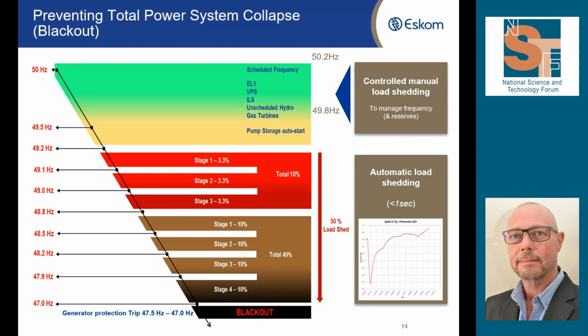What you see in this graphic in front of you now, we have the green portion, which is what I've just described. This is kind of normal operations where things happen fairly slowly, minutes to hours, and we dispatch various generation and demand response products. We then have a first breakpoint at 49.5 hertz, and that's where we would automatically start up some of our generators if they had not started already. Again, I'll come to the pump storage now, but those are some of our go-to plants. Remember I said that they can ramp extremely fast. So we do automatically start those at about 49.5 hertz.